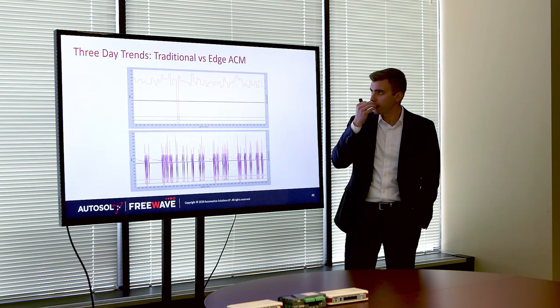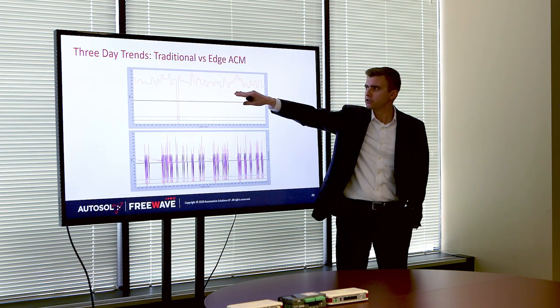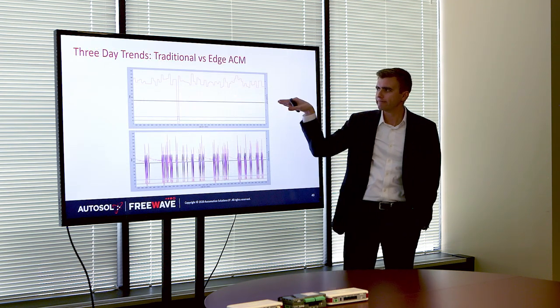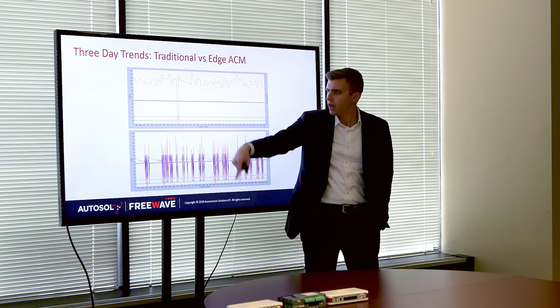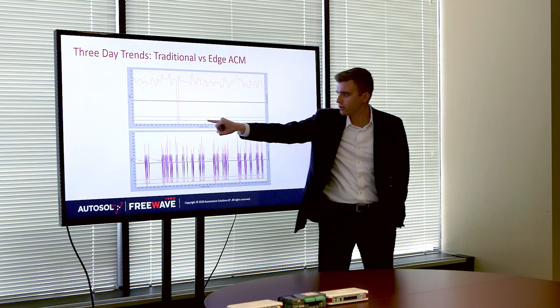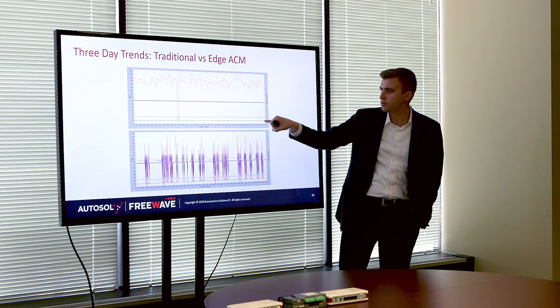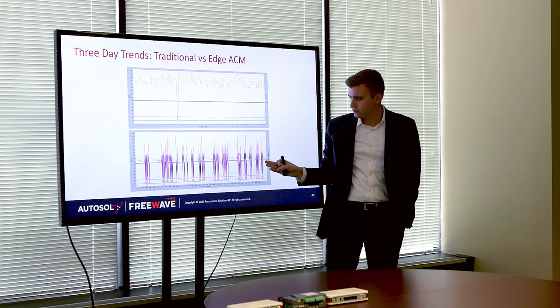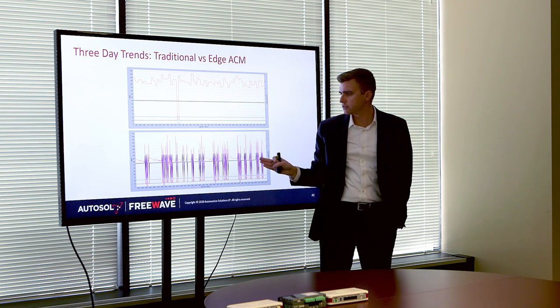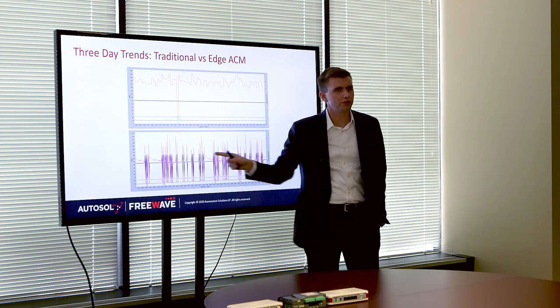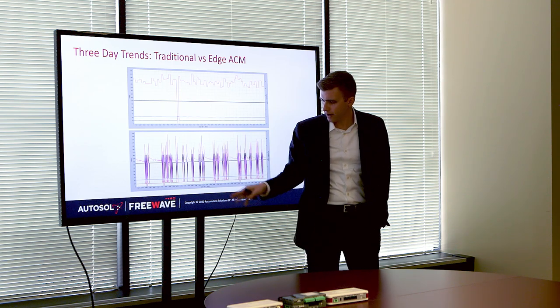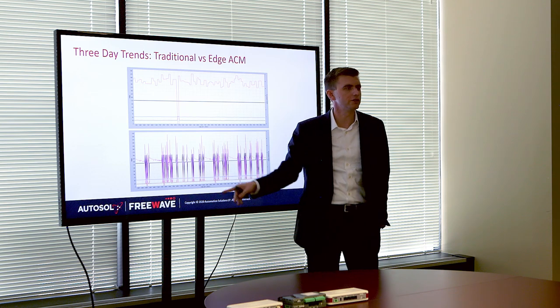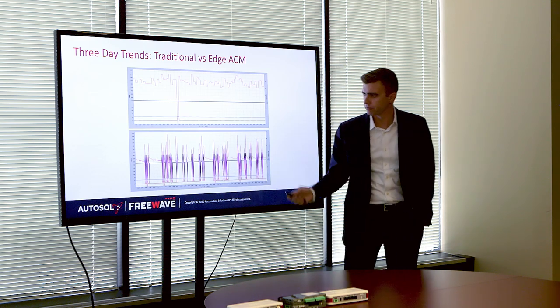Here's a bigger comparison of three-day trends. With traditional polling they missed every single plunger step and almost every change of all the different tubing and casing pressures. With Edge ACM we basically captured everything that happened — every plunger step, every change of flow rate, and the relationship between flow rate, plunger step, and pressures very nicely.